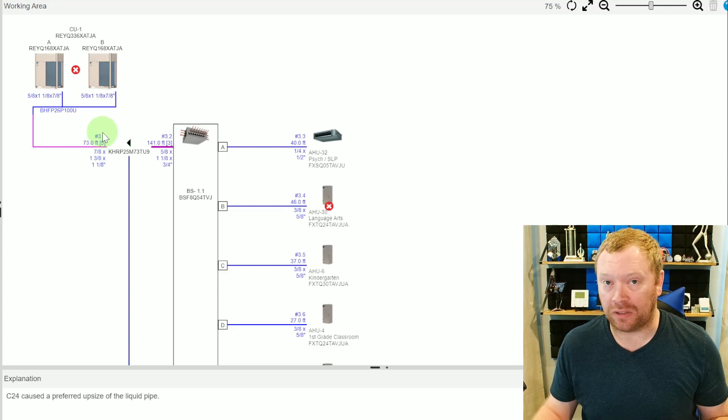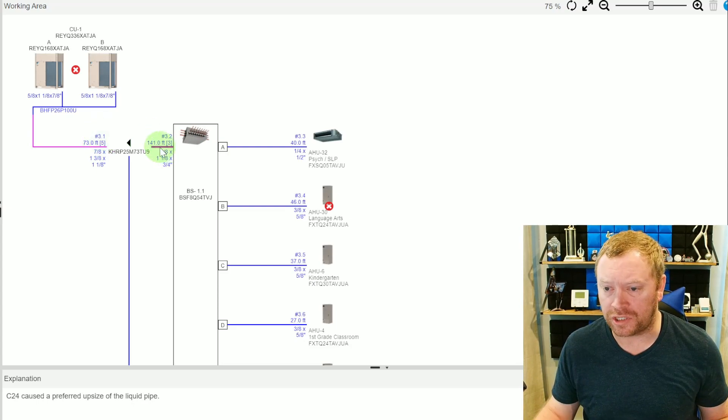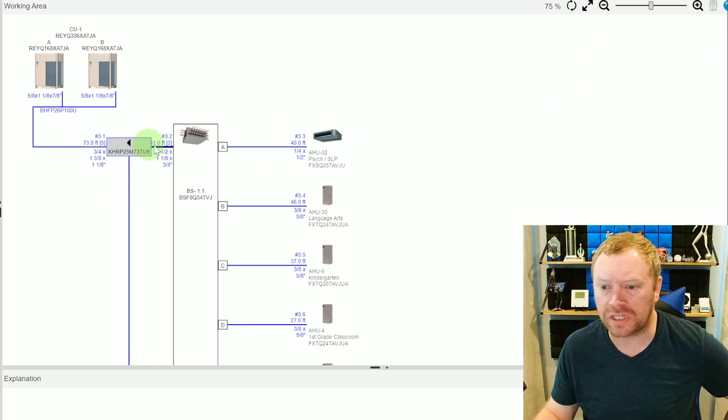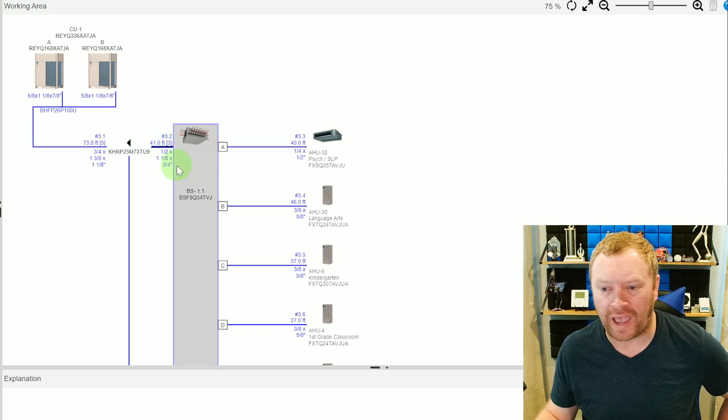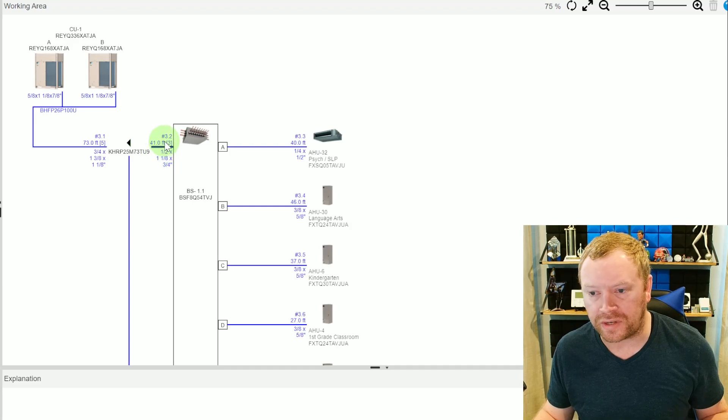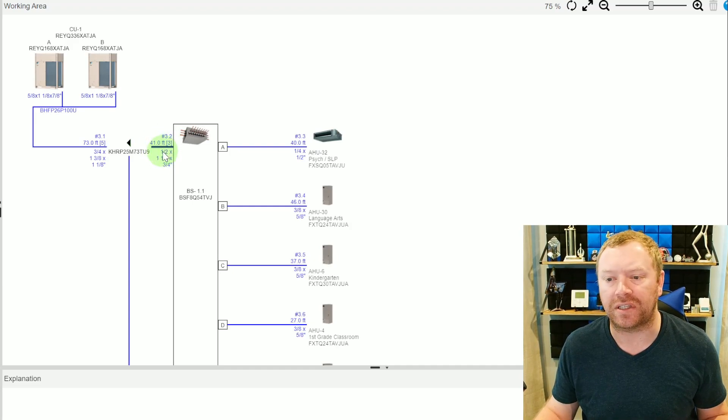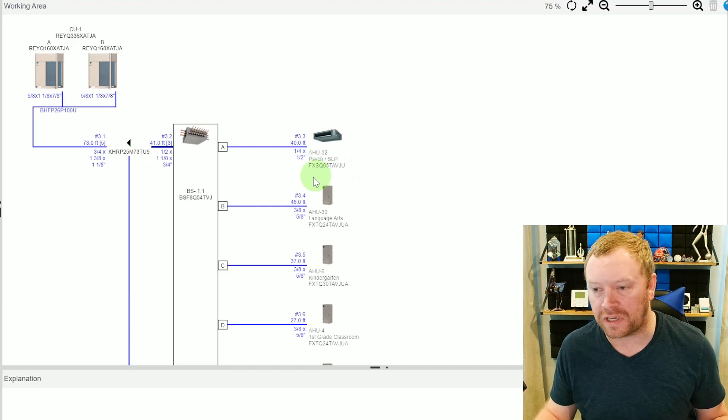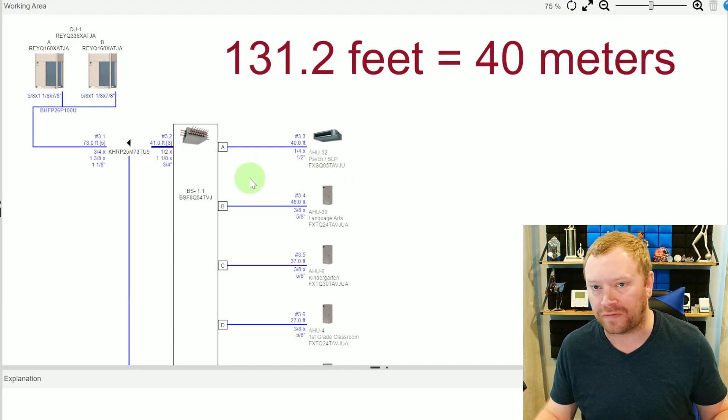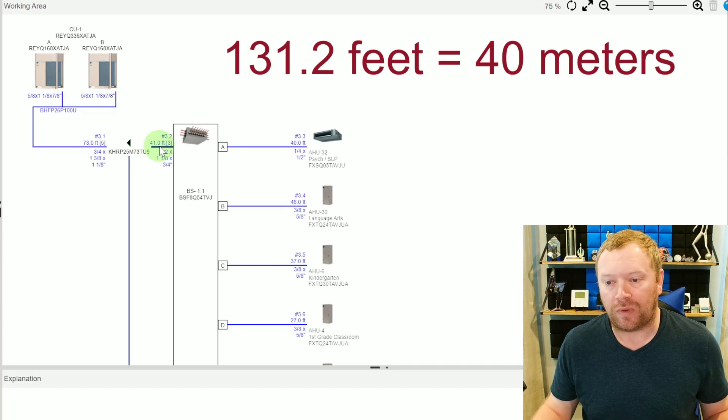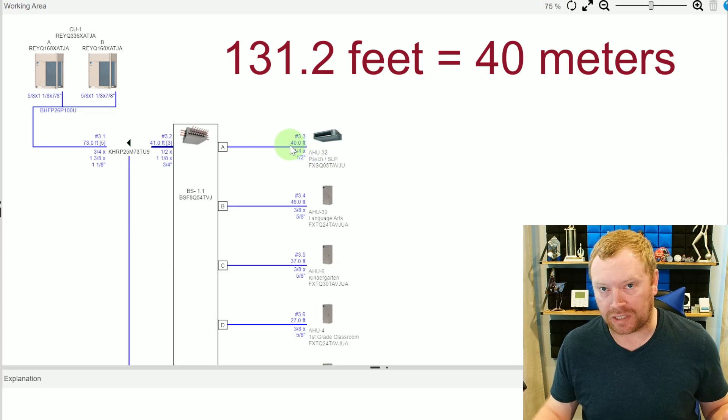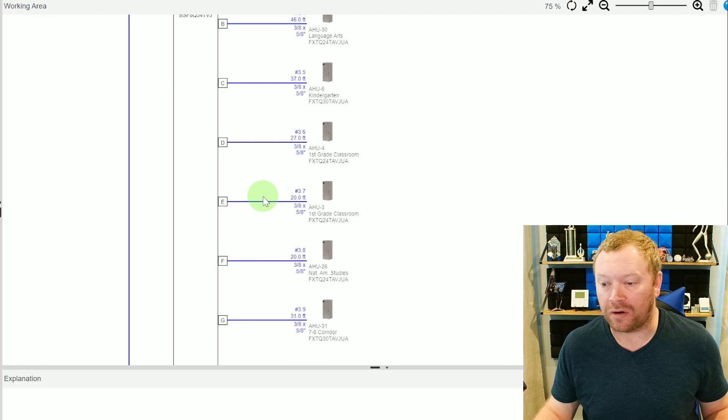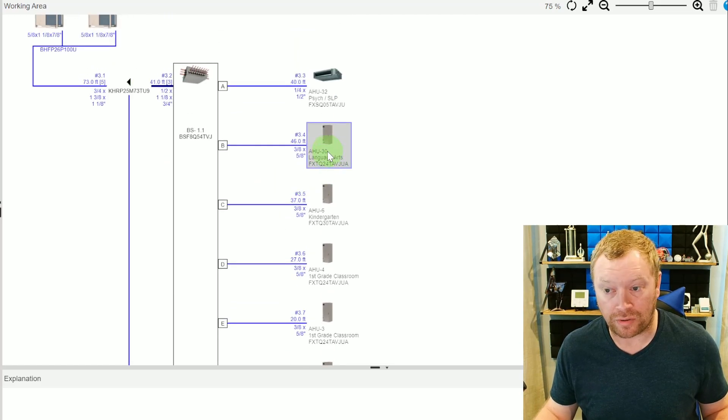Something else to consider is, let me go ahead and change this back to 41 feet real quick. You'll see that at 41 feet, we have half, one and one eighths, three quarters. And the initial rule that typically pushes this up is the length from the branch, the furthest indoor unit, it can't exceed 130 feet, plus or minus, it's converted from metric to feet. But when you exceed 130 feet from the branch to the indoor unit, that's what causes that upsize change.